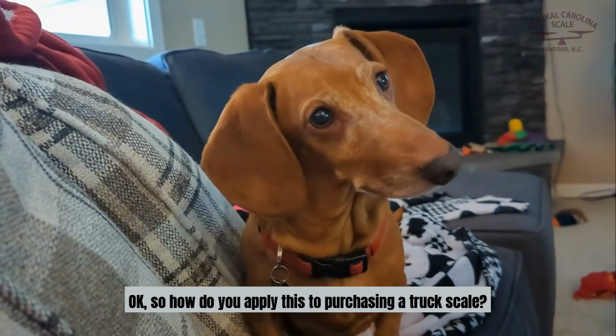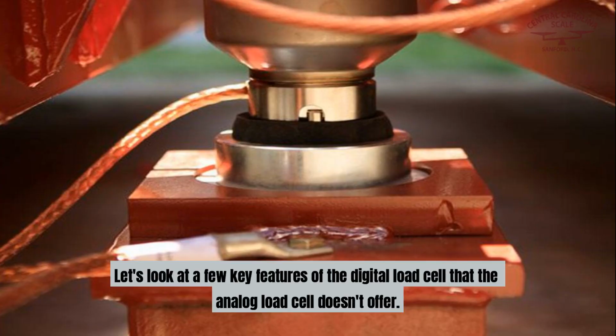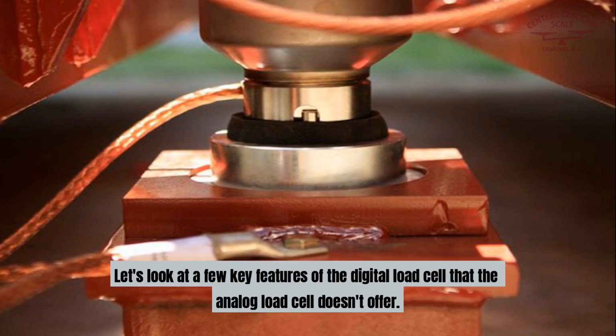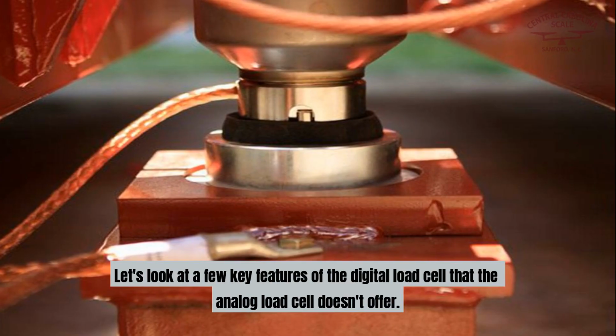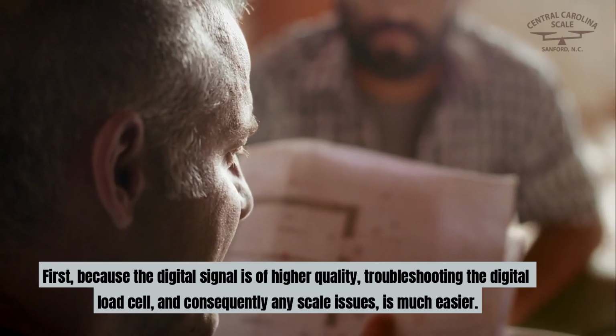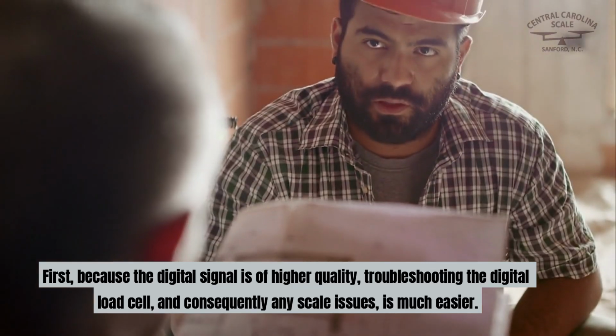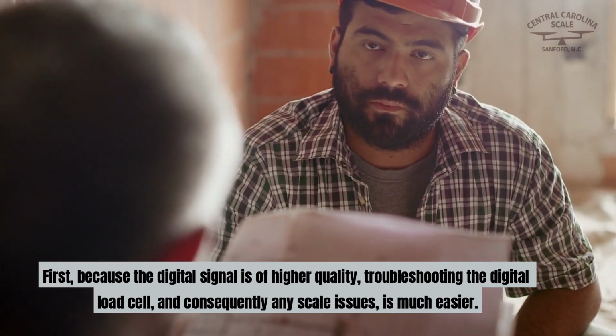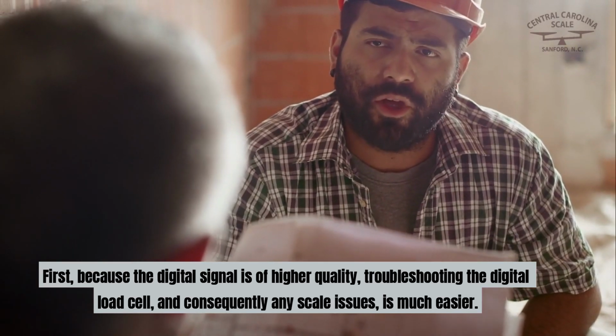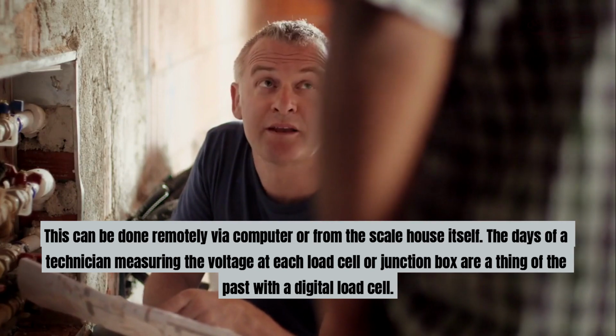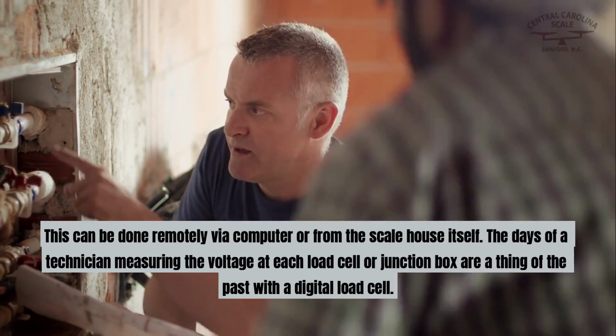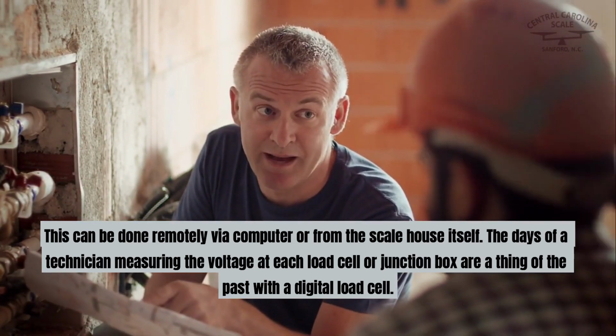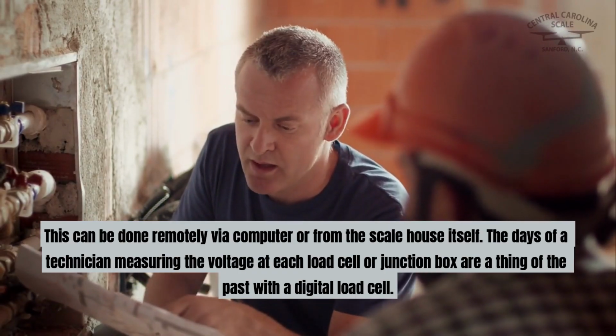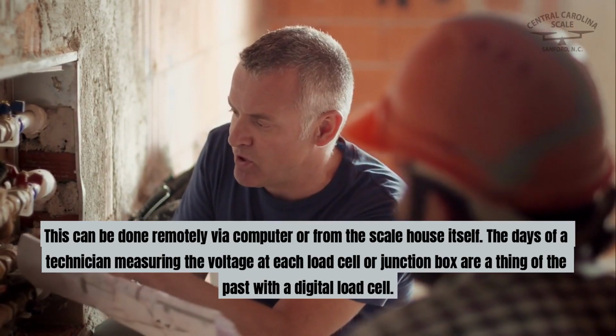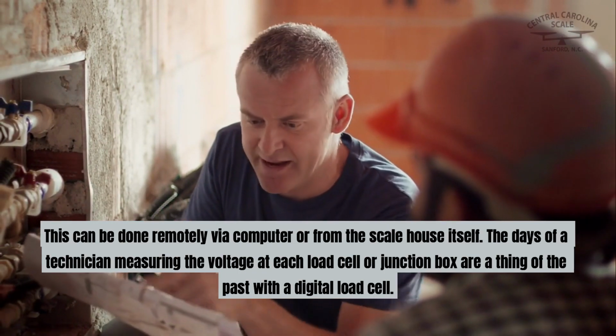Okay, so how do you apply this to purchasing a truck scale? Let's look at a few key features of the digital load cell that the analog load cell doesn't offer. First, because the digital signal is of higher quality, troubleshooting the digital load cell, and consequently any scale issues, is much easier. This can be done remotely via computer or from the scale house itself. The days of a technician measuring the voltage at each load cell or junction box are a thing of the past with a digital load cell.